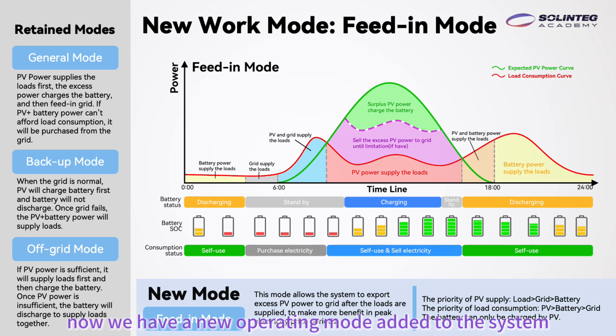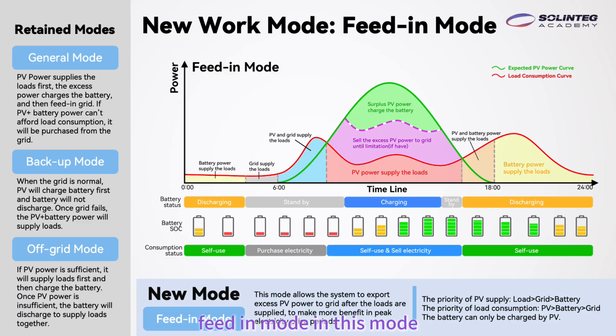Now, we have a new operating mode added to the system: feed-in mode. In this mode, the system prioritizes supplying loads first, then feeds any surplus PV power directly to the grid, making it particularly well-suited for sites in markets with favorable feed-in tariffs or high peak export prices, and the system will use the extra power to charge the battery. The battery in feed-in mode is only charged by PV. The left side serves as a quick reminder of the 3 retained modes from the previous generation: general, backup, and off-grid, each following their own priority logic to suit different site requirements.